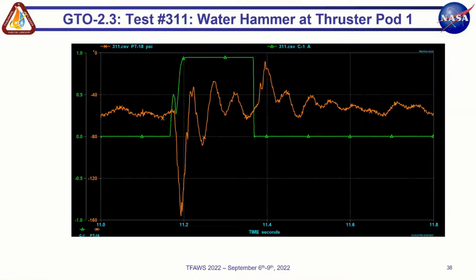So what we're seeing here is over this short time span, the same test series I was showing previously, we are able to actually see the beginnings of a pressure wave forming as a result of the valve opening. A little harder to get the same result here, and in hindsight, that was because we had not designed our data acquisition system to get high enough sample rates to really capture this effect. So we're aware of that as a lesson learned going forward. If we want to get better water hammer data, we'll make some modifications to this on future work.